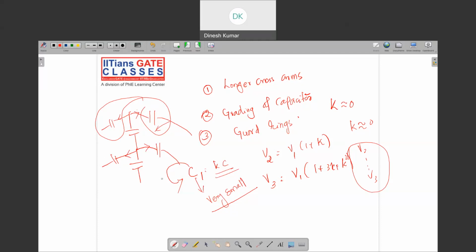This process is known as a guarding ring. So we keep some kind of rings very close to the conductor, something like this, so that there will be another capacitor, another current flow. You can check the figures of the guard rings to see how it is working. You can just check the insulator, what you normally see, there will be some kind of metallic thing. You just keep it like this. These are known as guard rings. This is used for improving the string efficiency. Okay, so you can write down all these things. After 1 minute, we will start again.